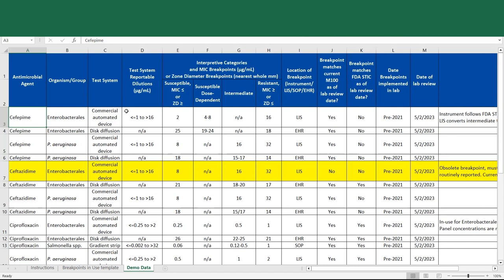Sometimes the full range of concentrations that may be on a panel are not always able to be reported for all organism groups. So that's why you need to know what the reportable dilutions are for a given organism group. And your technical representative should be able to assist you in finding this information if it's not listed in a product insert.